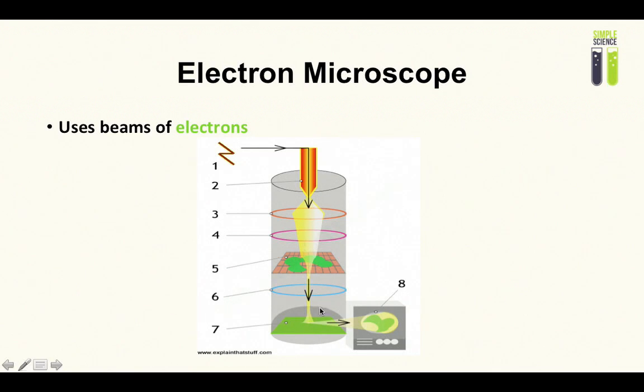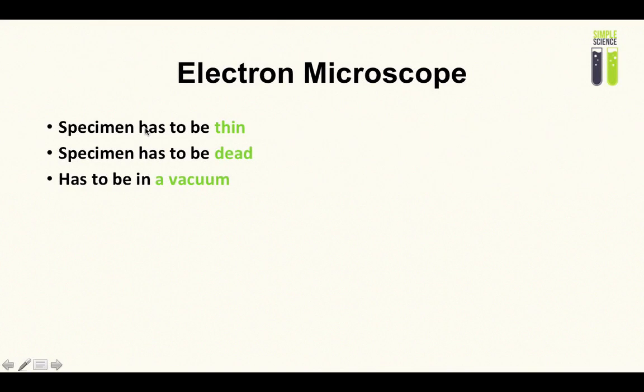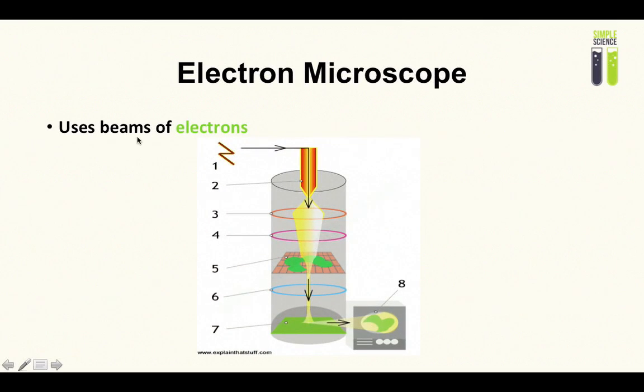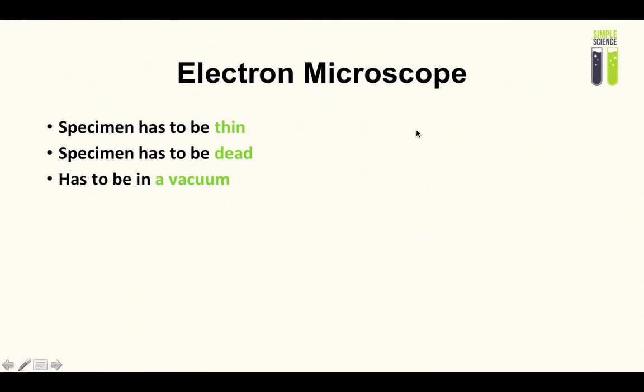Now let's get to why I mentioned that it needed to be in a vacuum. It has to be in a vacuum because we're working with electron beams. When an electron beam is traveling, if there are a lot of air particles it's going to collide and scatter and you're never going to get a clear image or a sharp image, so it defeats the whole purpose. For that reason the specimen also has to be dead because water boils at room temperature in a vacuum. So the specimen is dehydrated and it has to be dead. These three main things - vacuum, thin specimen, and dead specimen - are what you need to remember for an electron microscope. These are the disadvantages over a light microscope.